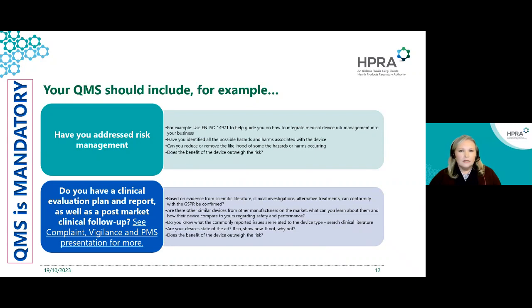What we usually see here is a risk management file. It would include things like hazard analysis, hazard evaluation, device and process failure mode and effects analysis, evidence that hazards that have been identified have been reduced or removed where possible, and that any remaining risks are acceptable. The risk documentation should conclude on the acceptability of the residual risks and make a call on whether the benefit of the device outweighs that remaining risk.